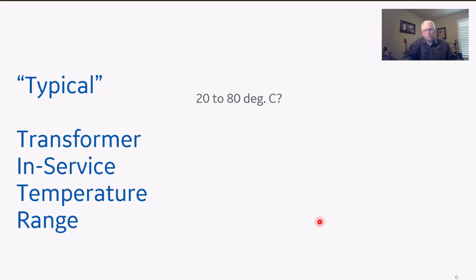You may have occasions with transformers, especially some I had down in East Texas, built back in the 1930s and 1940s, that were constantly overloaded to 120%. They'd get a little warm. The way they designed those transformers back then, you could actually run them a lot hotter. But typically, if you go into a substation today and look at temperatures on a transformer - top oil, main tank, windings - you're probably going to find these things operating somewhere between 20 and 80 degrees C.